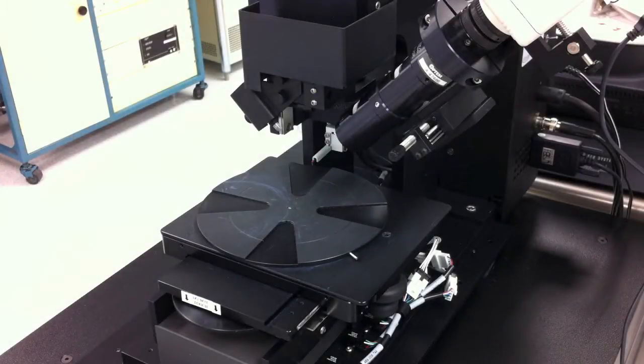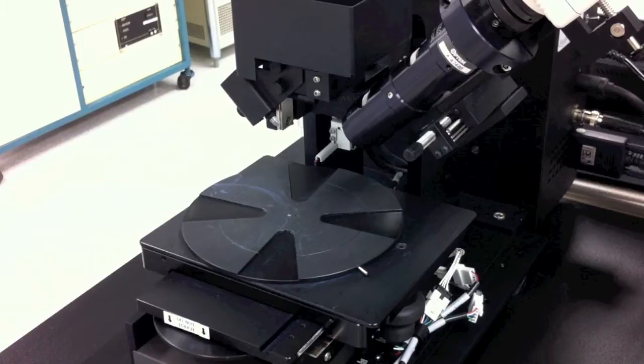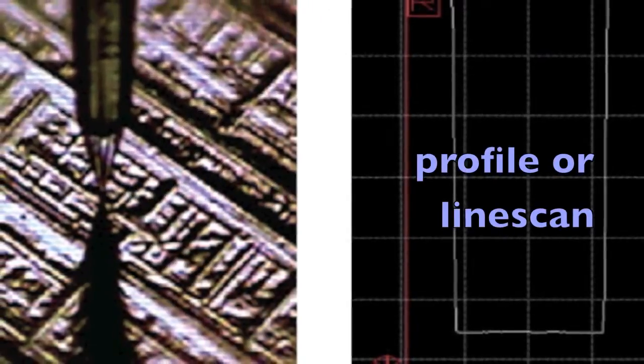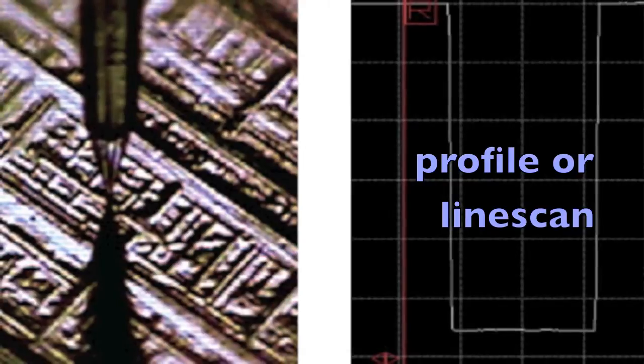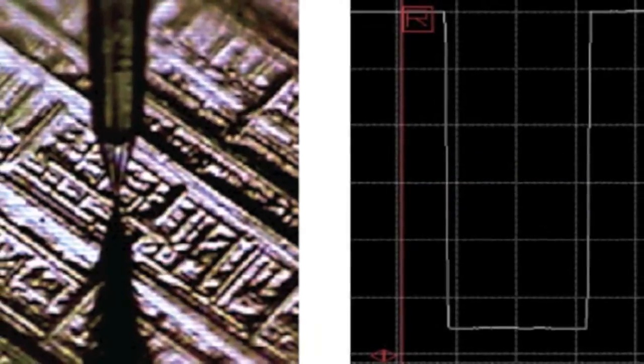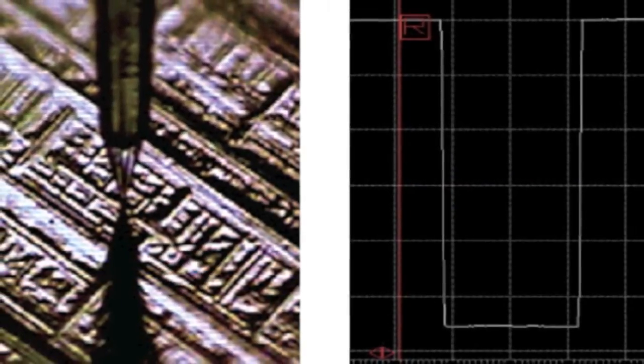Introduction to Profilometry with the Veeco Dektak 6M Stylus Profilometer. Profilometers allow us to measure topographic features because they use a probe with a radius typically on the order of 10 microns to make physical contact and raster across a sample and produce a profile or line scan. By plotting the probe movement both laterally and vertically, users are able to take height and width measurements.